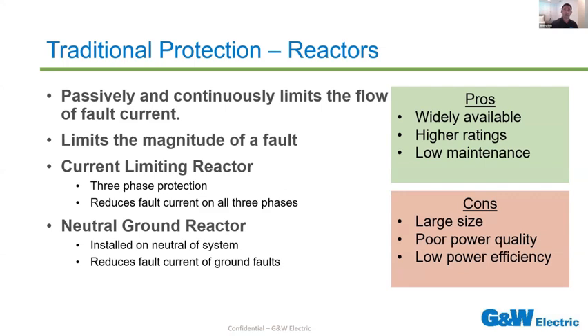Next slide, please. Another set of traditional protection components are reactors. They are passive and continuously limit the flow of current. It's very important to emphasize that with this solution, you limit the fault, but not the duration of the clearing time of such a fault. The operation, or the application, is that you are introducing an impedance into your system. Two examples of these are the current limiting reactors for three-phase protection, and the second one is the neutral ground reactor that, as the name states, limits the fault from line to ground.